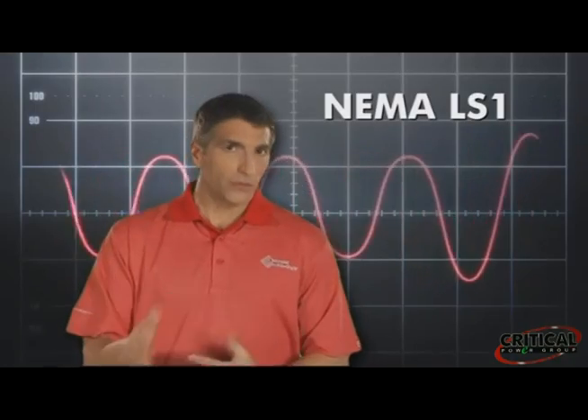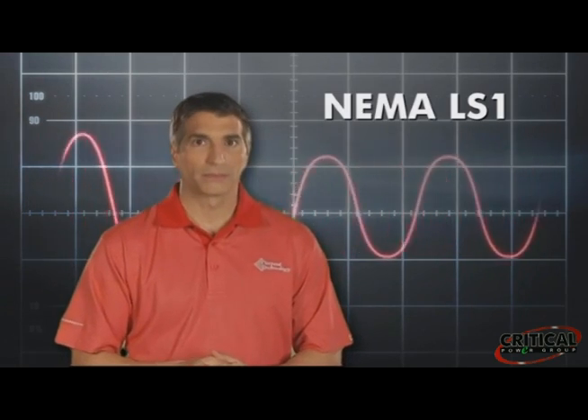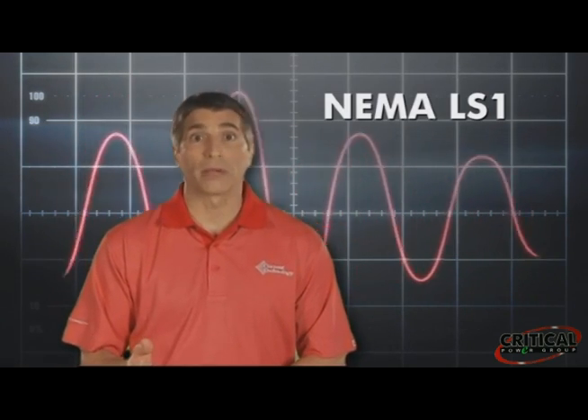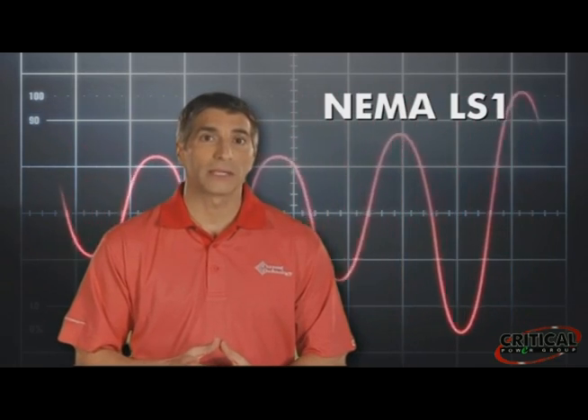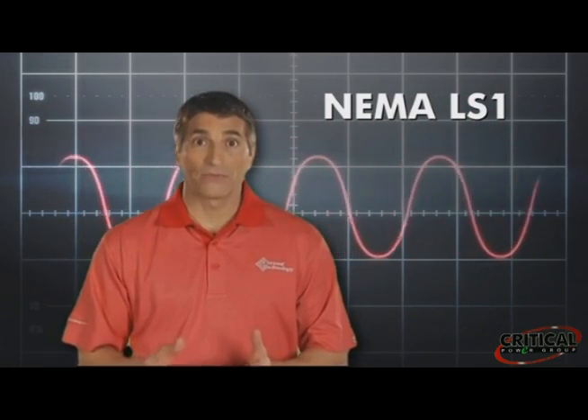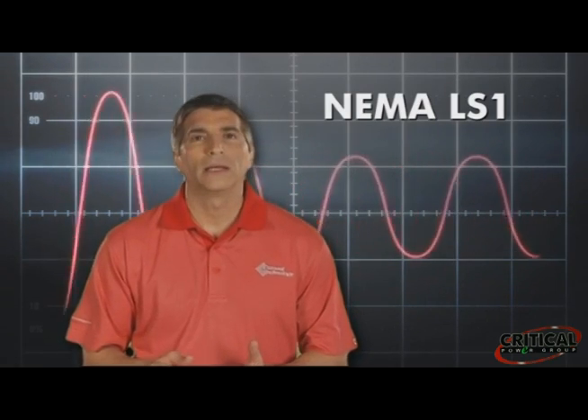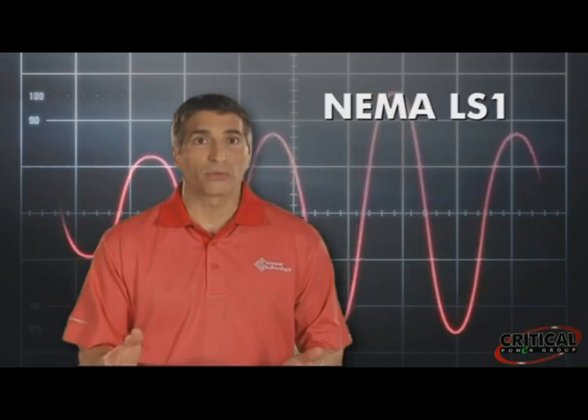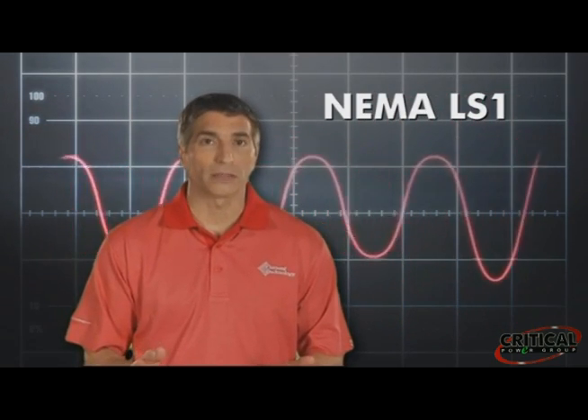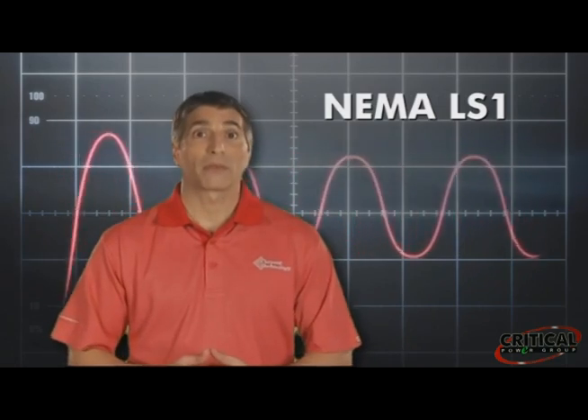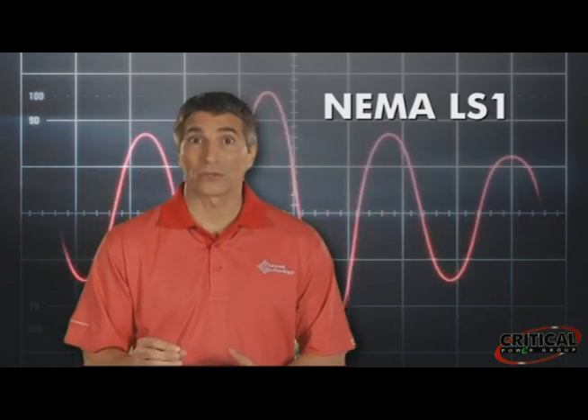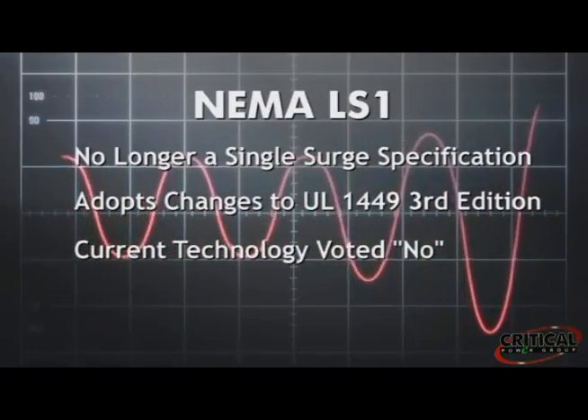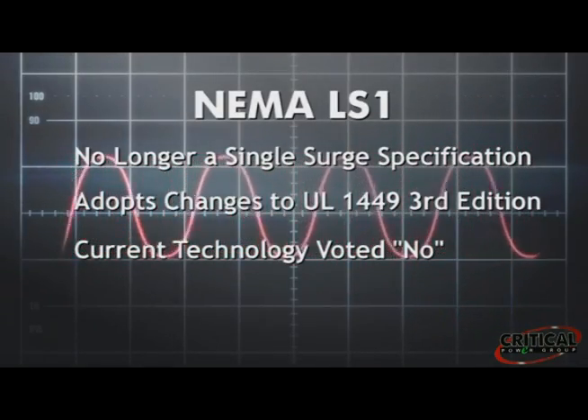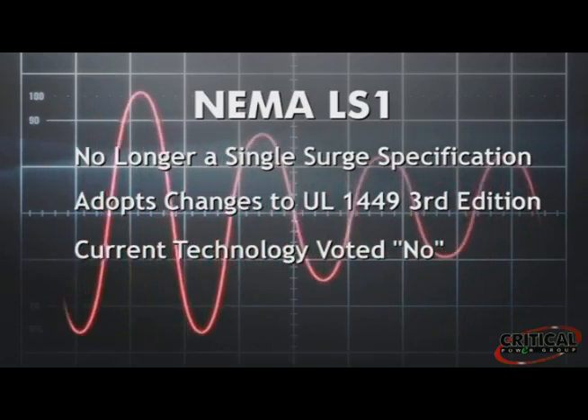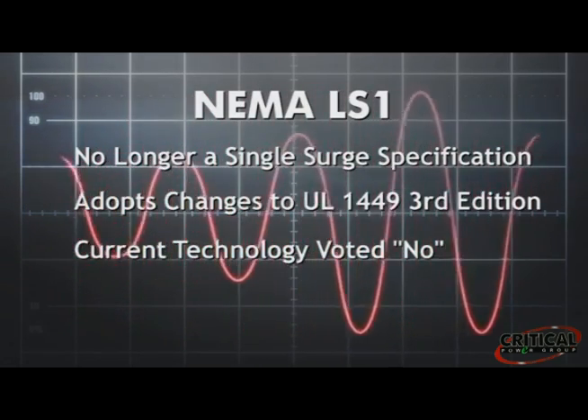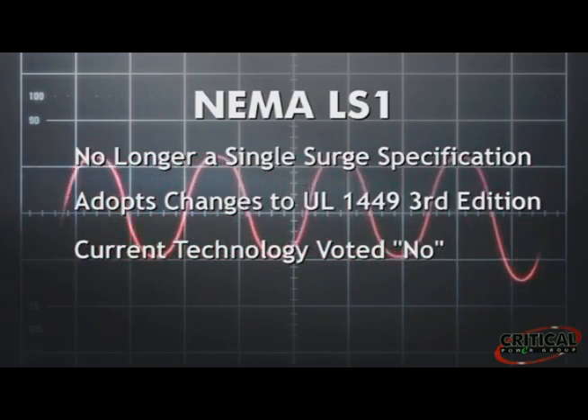Another issue you should know about concerns NEMA LS1, a standard published by the National Electrical Manufacturers Association concerning SPDs. You should know that some manufacturers have voted to reduce the standards of NEMA LS1, to no longer require a surge test that will prove a unit's ability to handle the claimed single surge rating. Why? Perhaps it's because their products can no longer meet the single surge rating they claim for their products. They merely want to base their products' ratings on the number of MOVs their system has, instead of industry standard performance results per NEMA LS1. Current Technology was among only a handful of manufacturers that voted against lowering the standard.